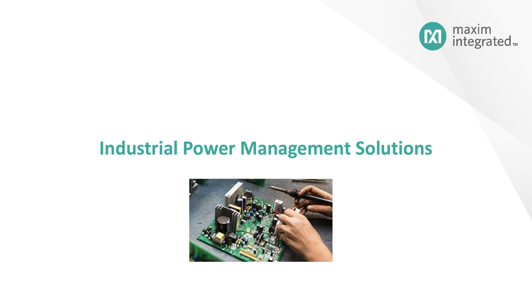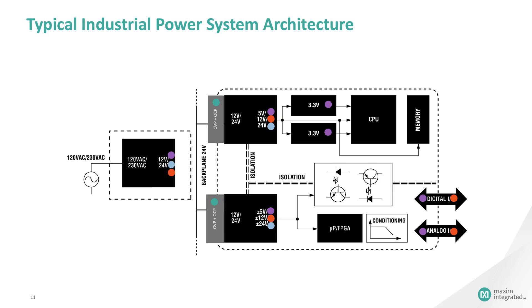Next is industrial power. Let's start with the general industrial power system architecture. Many industrial systems start with AC power in, which is then converted to a DC backplane of 24 volt or 12 volt. With this backplane bus, power is supplied to various IC components that may need 3.3 volts, 5 volts, 12 volts, or any other such voltage. Buck-boost converters and modules perform this power conversion at very high efficiencies. In many cases, the power has to be isolated using magnetic isolation to protect the downstream components.